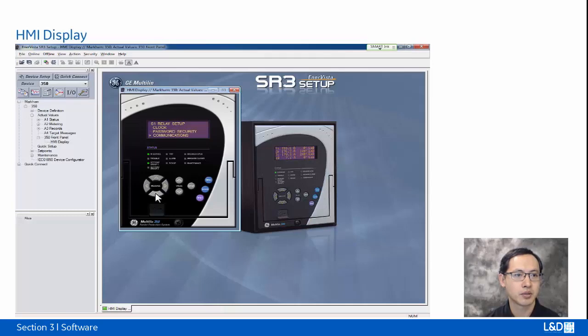For example, we can go to the relay setup and set the front panel installation. So from the installation we can select the relay name, status ready. We can change from ready to not ready, and press enter. So once we saved this relay not ready, we can see that the trouble light turned on.